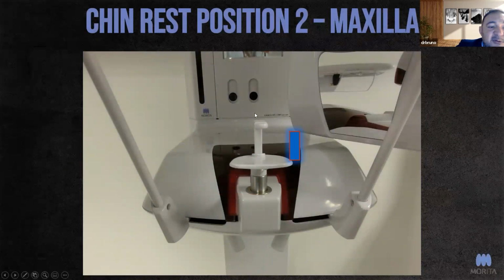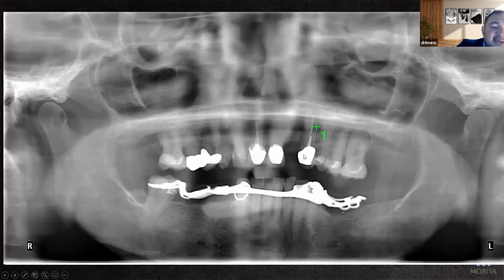So how do I get to position 2? Instead of dropping this straight down, turn the bite block to the right, then drop it into this little hole here, and you can see the chin rest is going to drop about half an inch. That is the clearance that a lot of times you need to clear the shoulders on larger patients. But most importantly, that's the clearance that allows you to go to the maxilla and not have the box turn red.